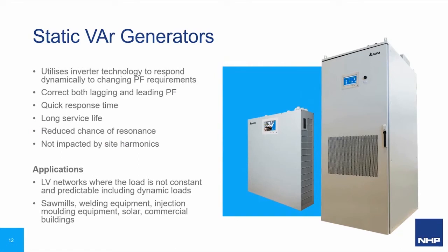First up, we have static VAR generators, also known as SVGs. These are based on inverter technology to respond dynamically to changing power factor requirements. They can correct both lagging and leading power factor. They have a very quick response time, long service life, reduced possibility of resonance, and are not impacted by site harmonics. In general, in terms of applications, these are best suited for low voltage networks where the load is not constant and predictable. So places like the sawmill example from before, welding equipment, injection molding, and commercial buildings.